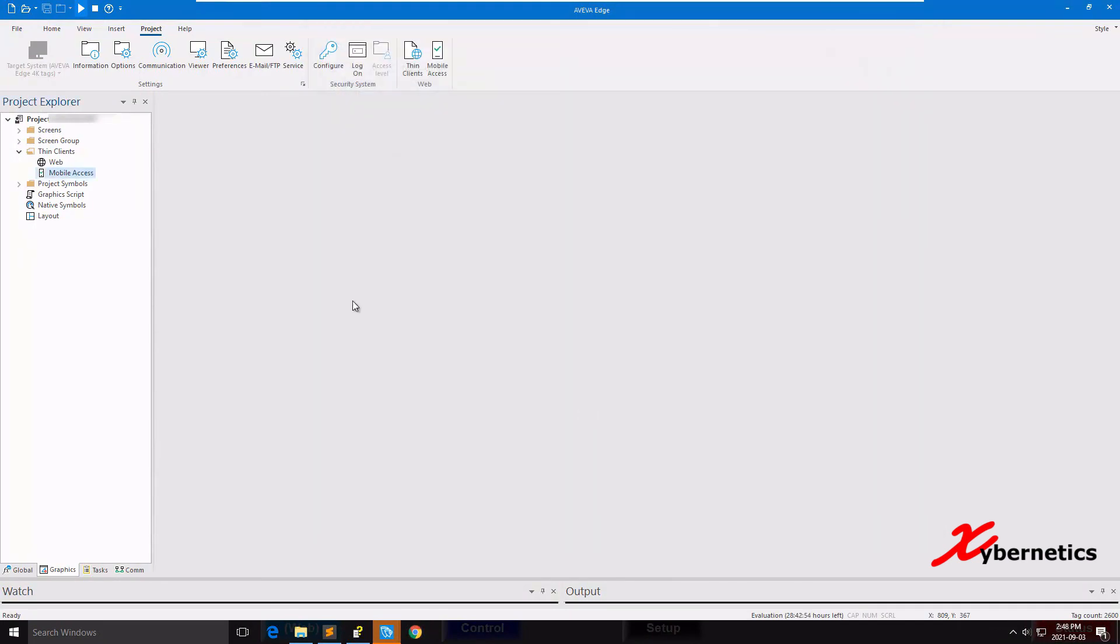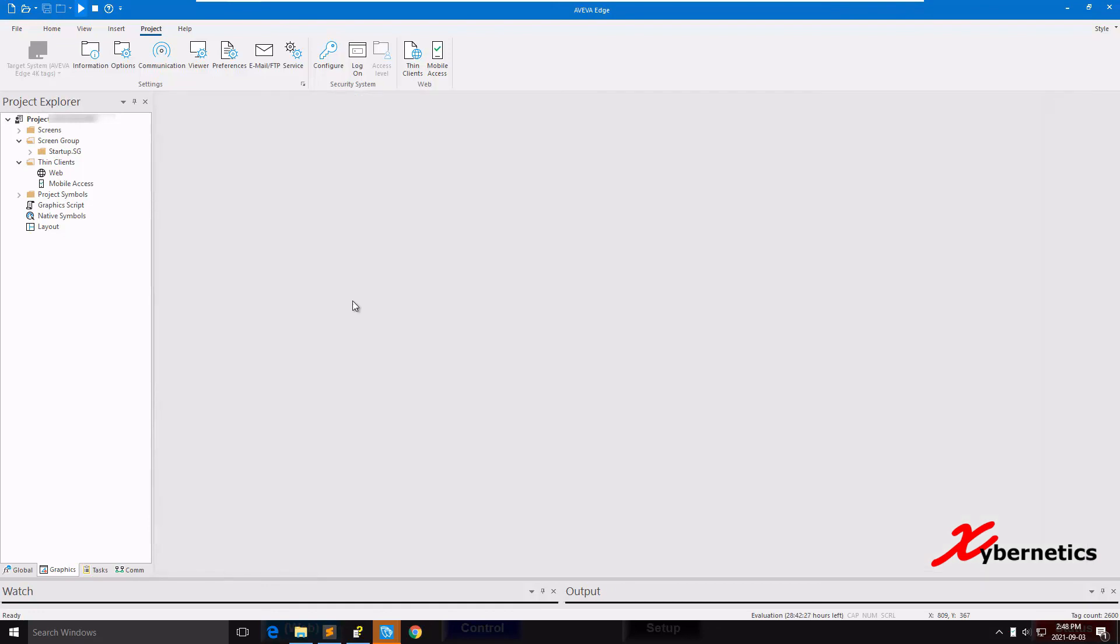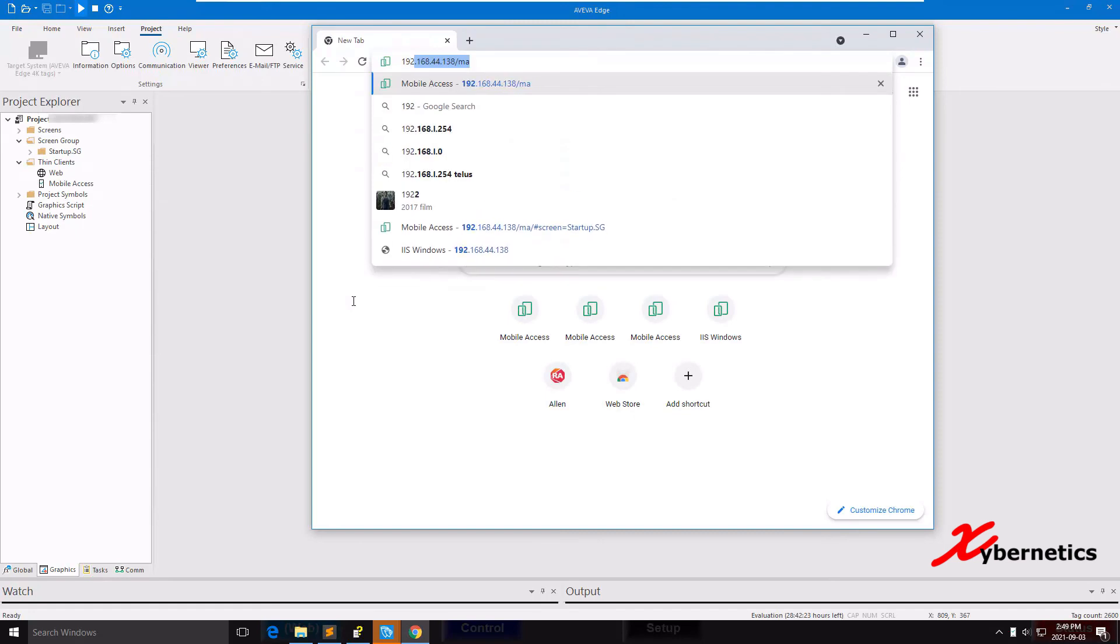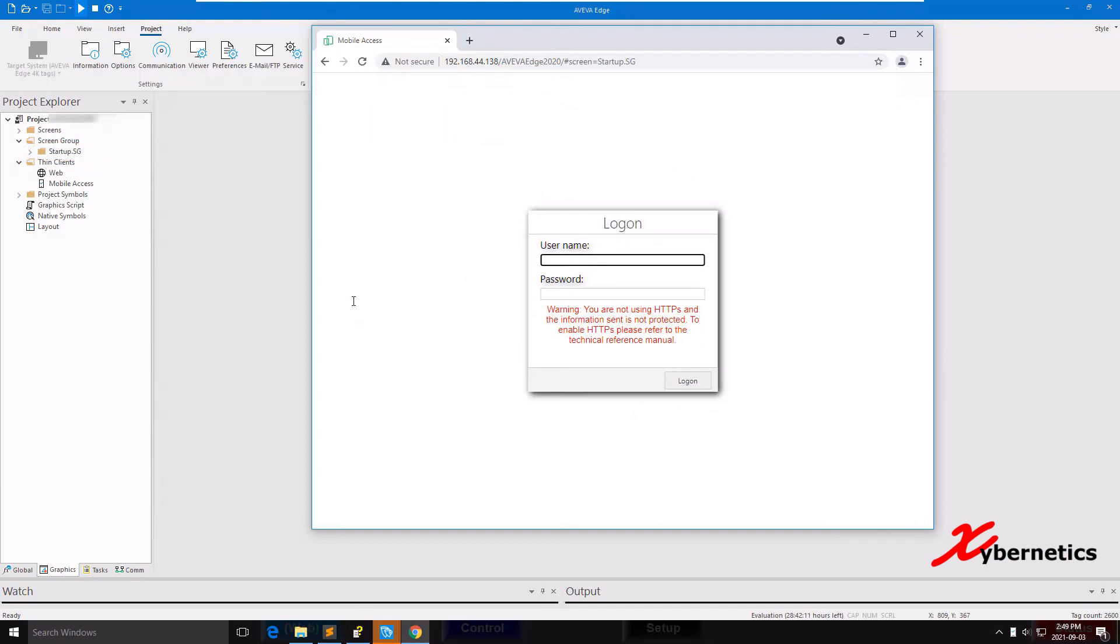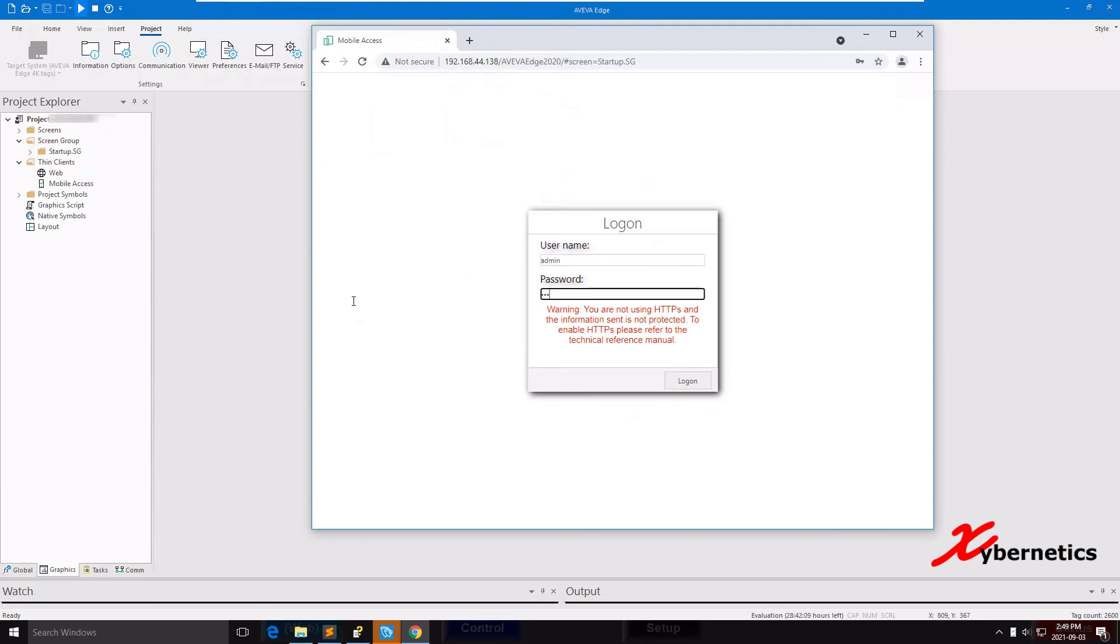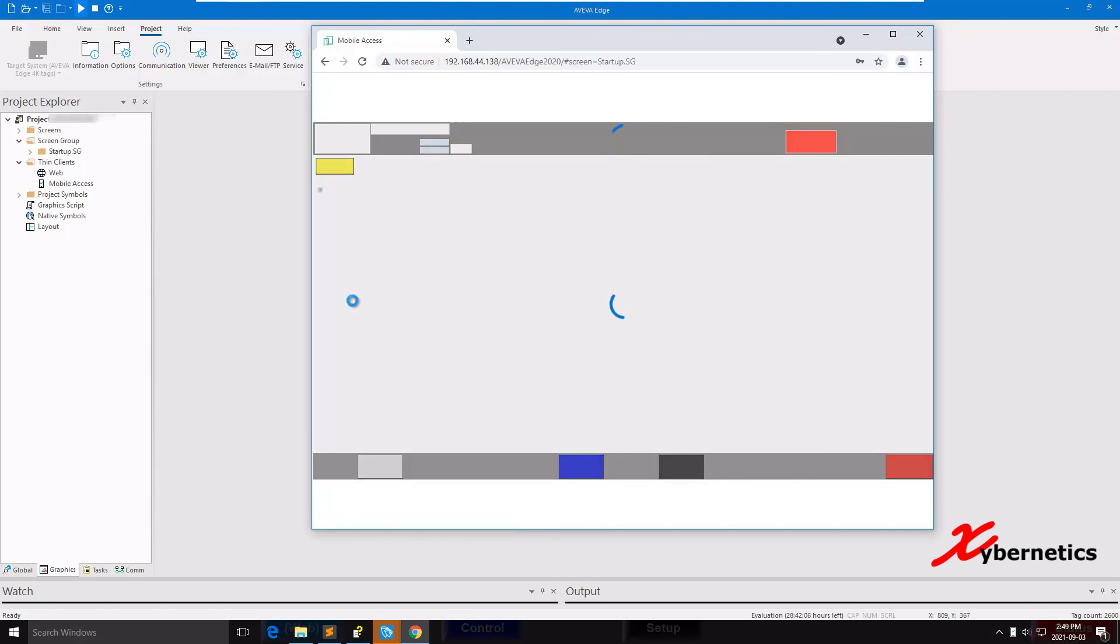A more efficient way to define and use screens on the mobile web access would be to define as a screen group. I've already defined a screen group here. Under this folder there's three different screens that I've specified. Once you specify the screen, select your screen group name, right-click and Save As HTML. Once that flashing of the screen is done, which indicates your screens are converted to HTML, open the browser and punch in your IP address slash MA, but this time hashtag screen equals startup.sg. This is the same name as this name here. Once that's done, hit Enter. They'll prompt you for user credential again. This time around it will start to load using your screen group.